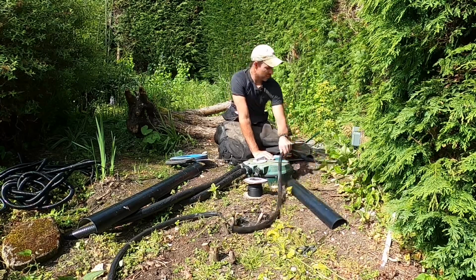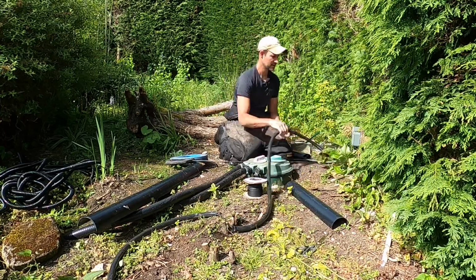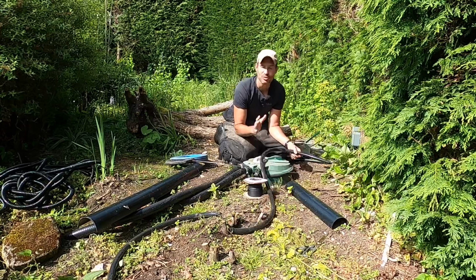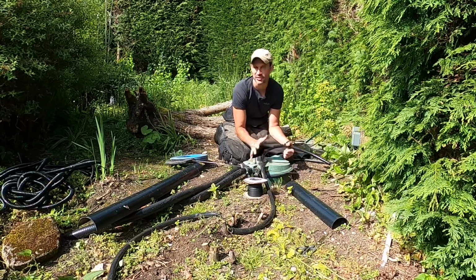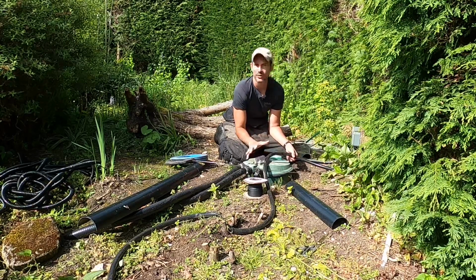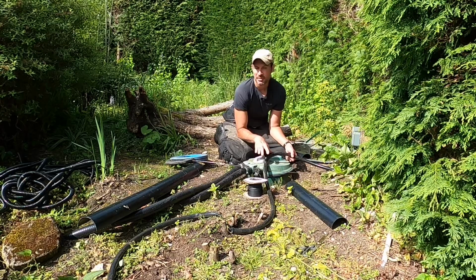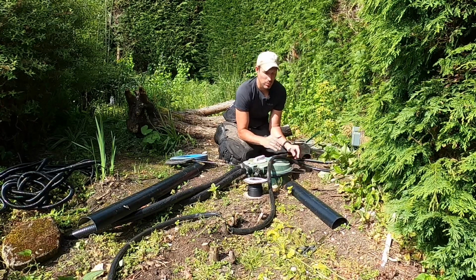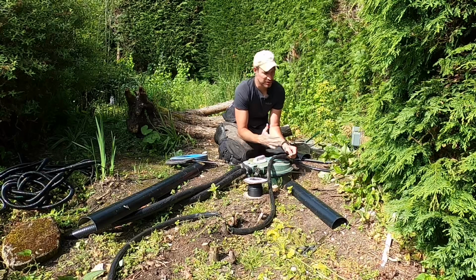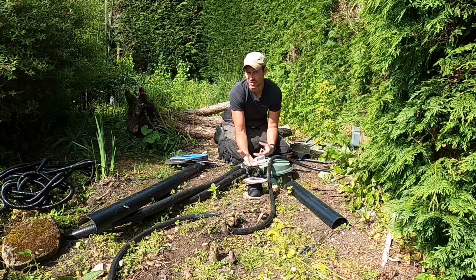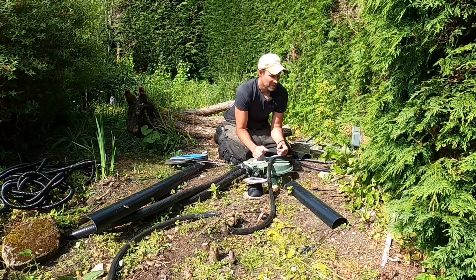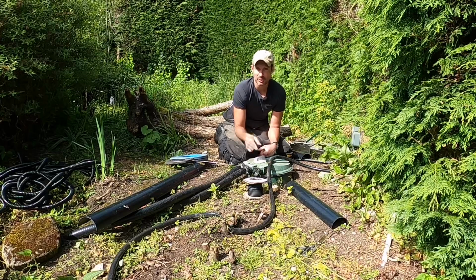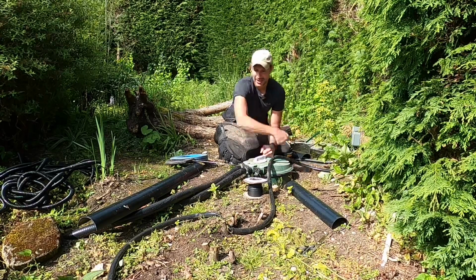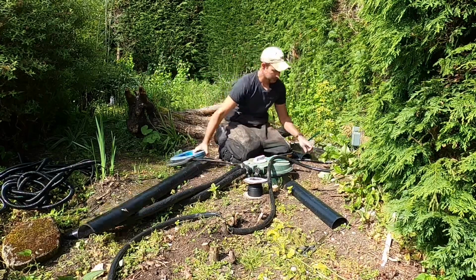To get the cable through the conduit, it's always very important to make sure you run cables through protective layers of conduit if it's going to be anywhere in the ground. I'm not so concerned in the pond itself, but certainly here, buried in the border, having a conduit means, one, it's protected, and two, in the future if you need to run extra cables through, like in this instance, or replace something, it's a much easier job being able to pull a cable through, attach a string to it, and then pull the new cable back through.